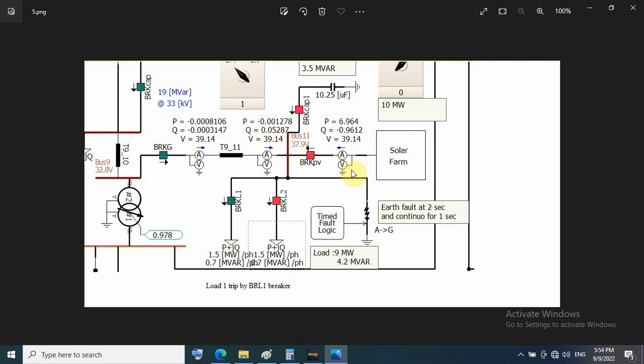For the last question about earth fault: because the transformer connection is delta connected on 33 kilovolts, the PV will not contribute any current to the earth fault.